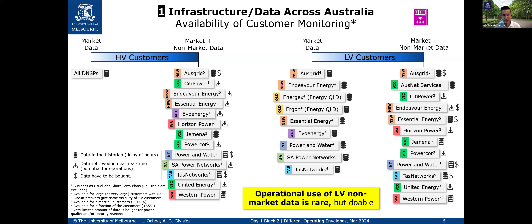In Victoria, where smart meters are owned and operated by distribution companies, they have access to both market and non-market data. But in other parts of Australia, those smart meters are operated by third parties — not the distribution company — which means the non-market data, meaning active power, reactive power, current and angle, needs to be bought. That creates challenges: you need to justify the expense and integrate data from a third party. It is still rare to see operational use of non-market data in the low voltage, but totally doable.